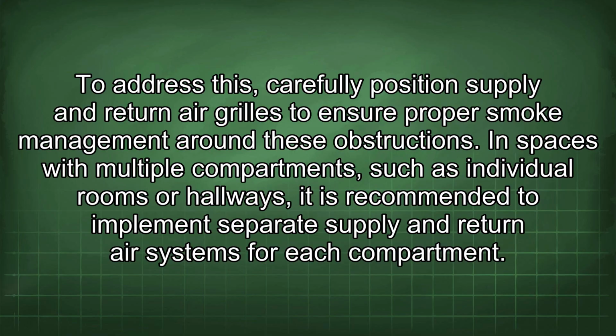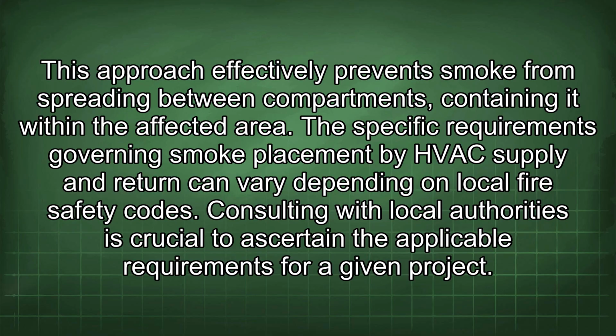In spaces with multiple compartments, such as individual rooms or hallways, it is recommended to implement separate supply and return air systems for each compartment. This approach effectively prevents smoke from spreading between compartments, containing it within the affected area. The specific requirements governing smoke placement by HVAC supply and return can vary depending on local fire safety codes. Consulting with local authorities is crucial to ascertain the applicable requirements for a given project.